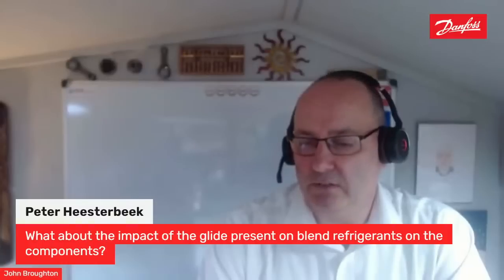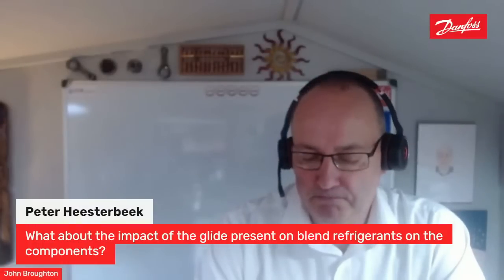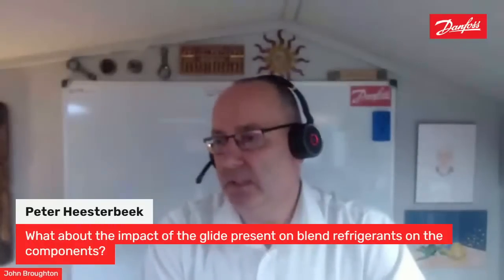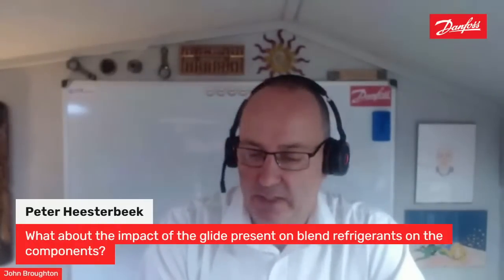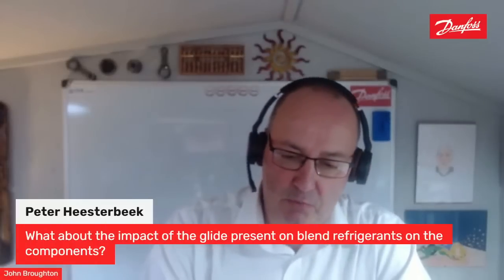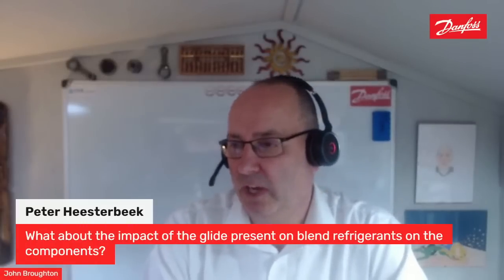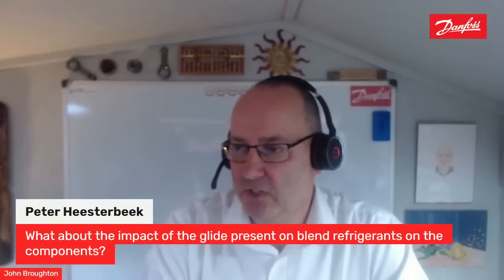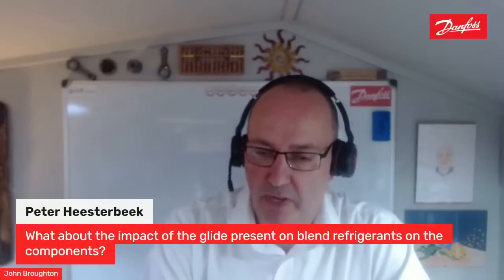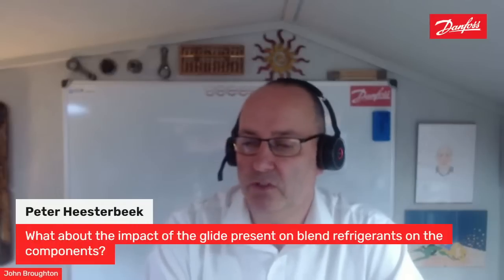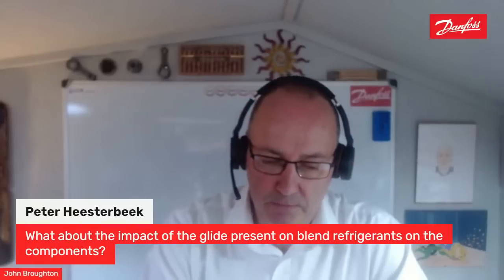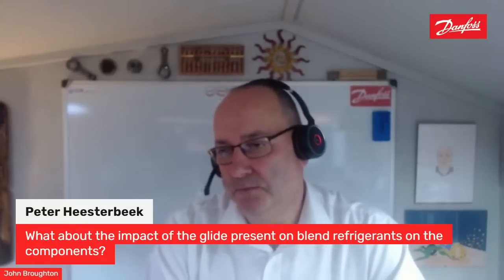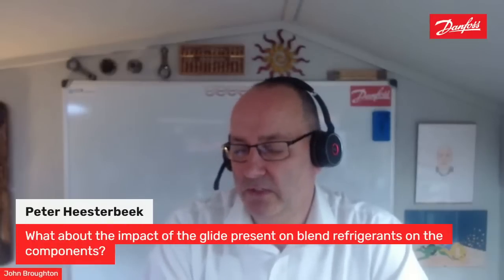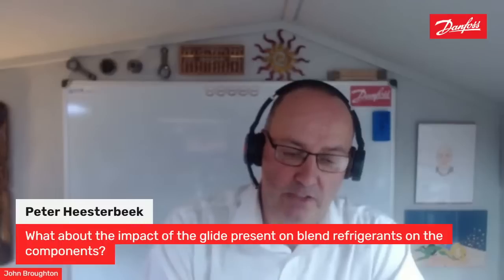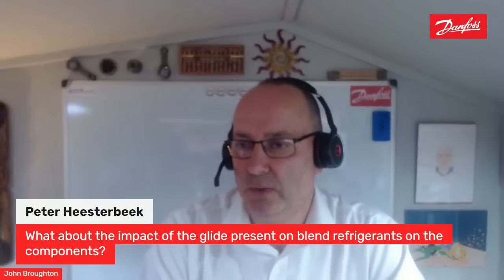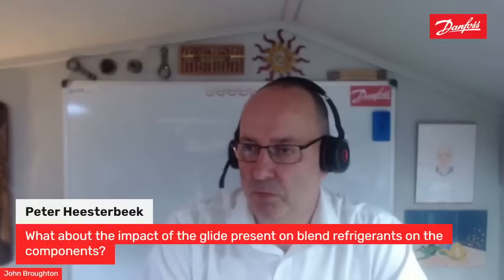Generally, I try not to get too confused about glide. Yes, we have glide on refrigerants. And if we're talking about expansion valves and operation of the compressors, that is taken into account when we do the selections. I think the biggest challenge regarding refrigerant blends is the different pressures and the different temperatures, and do we do it at dew or bubble? But when we do a selection, particularly in Coolselector, all that is taken care of with regard to glide. So hope that answers that question, Peter.